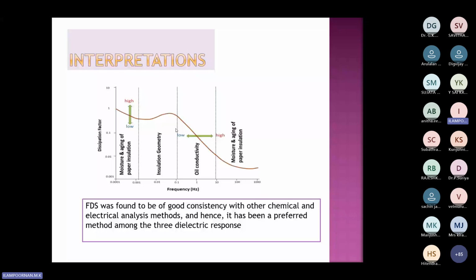Here I have shown the dissipation factor, which, as I have already shown, is the ratio of IR by IC. Why do I need to measure this ratio? I can directly measure IR. That will give more idea of this thing. That is one of my research conclusions. So I can measure IR directly and relate it to the actual problem happening in the transformer. That is my actual research work, my PhD work. And if I move slightly higher, from 1 millihertz to 10 millihertz, I can understand how they have designed the transformer.